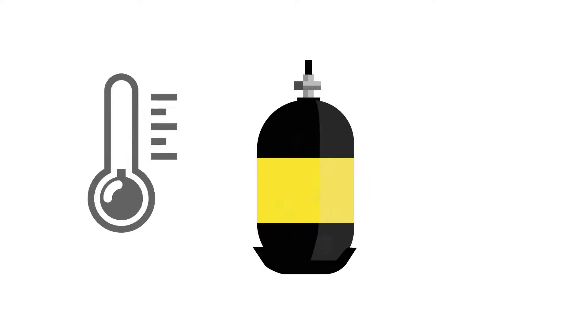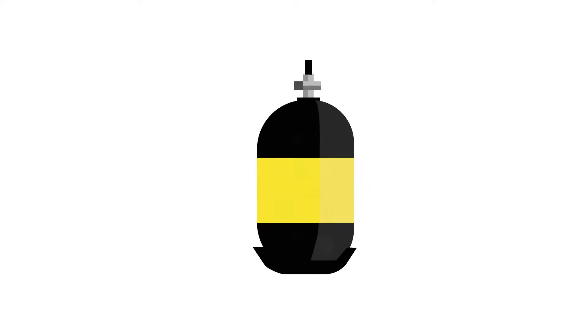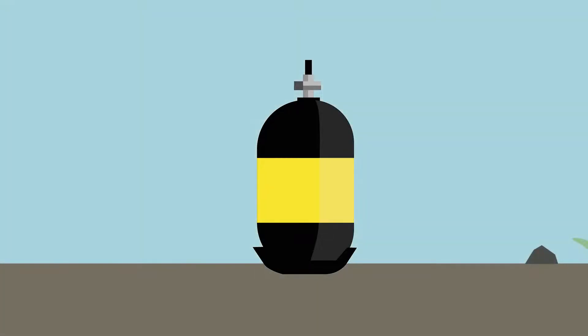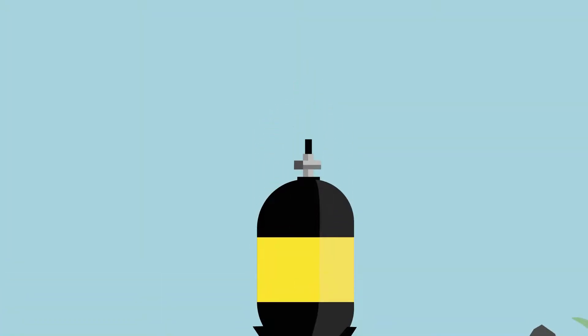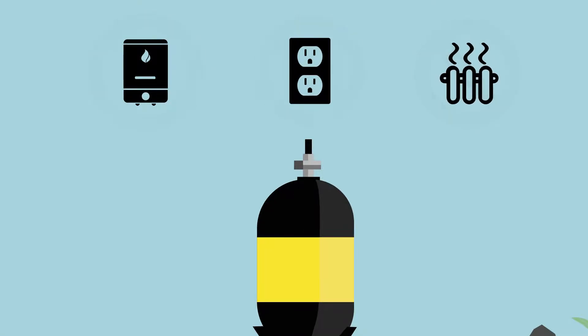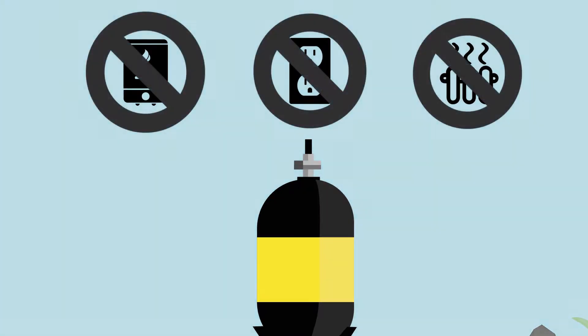Store the propane tank or tanks in well-ventilated areas and preferably outside and away from potential ignition sources like furnaces, electrical panels, and space heaters. If any anomalies are found, immediately contact your dealer for further instructions.